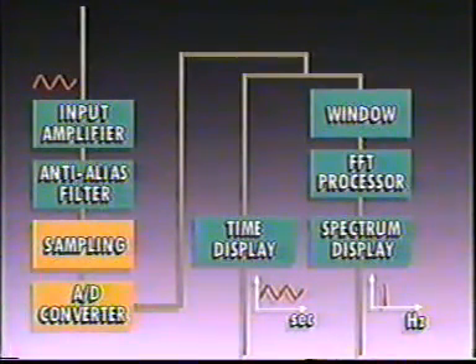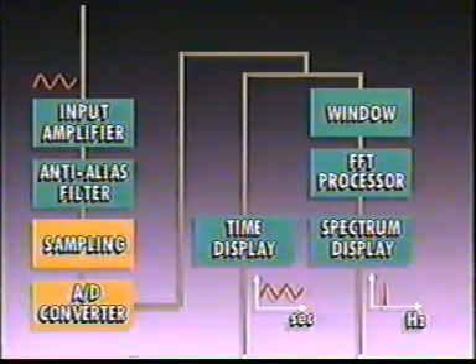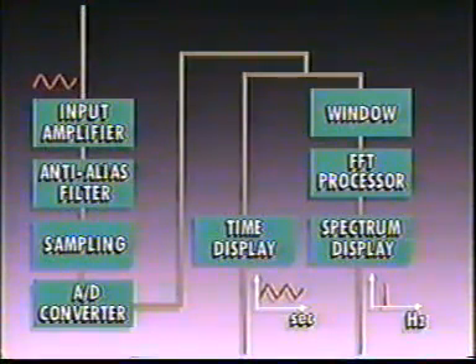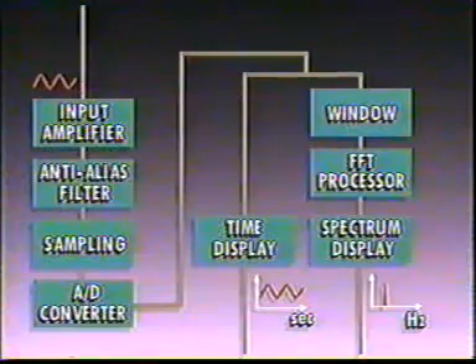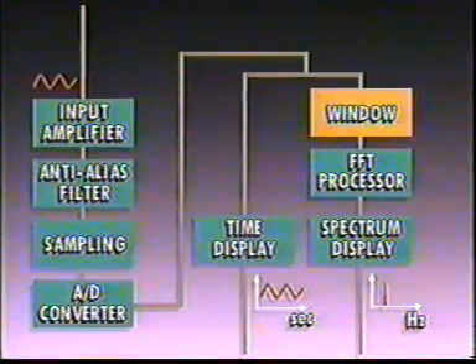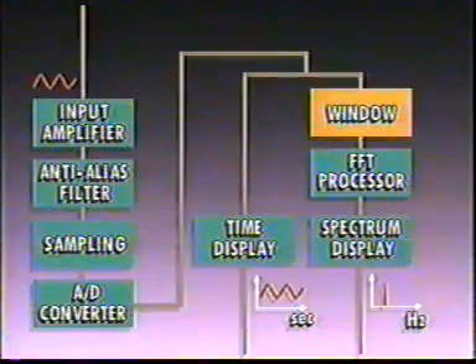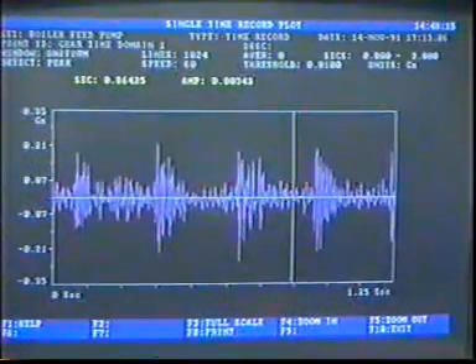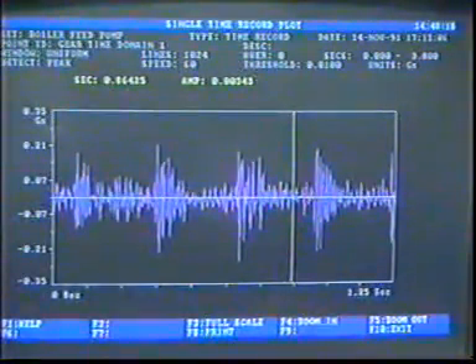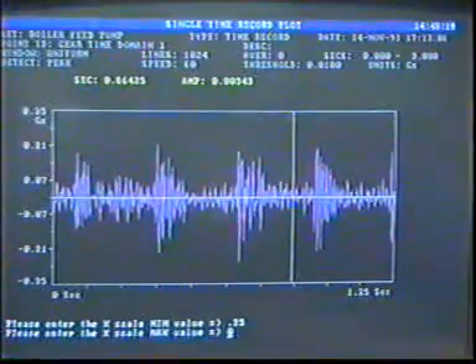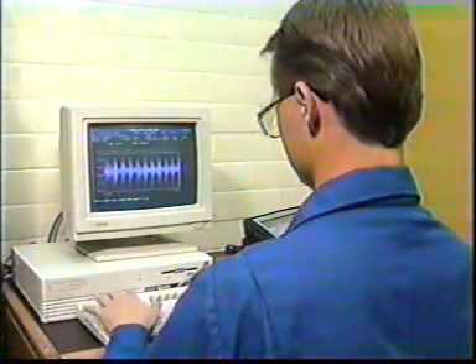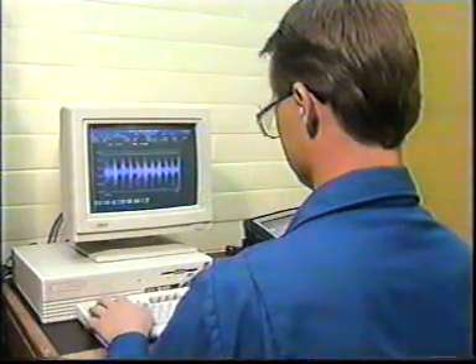Next, the sampling circuit captures a block of time from the composite signal, and the A to D converter digitizes the captured data. A typical analyzer samples thousands of voltage points per second. Now the operator can choose to see either the time domain signal, which should look like the input signal, or choose to look at the frequency domain. The window circuit prevents a leakage error if the sampled signal does not match from beginning to end. This means that the end of the sample signal must be of the same value and have the correct slope. If this automatic feature isn't present, the base will widen and not give a true representation for the signal. Aliasing and leakage are problems inherent to FFT analyzers, but they are automatically compensated for.